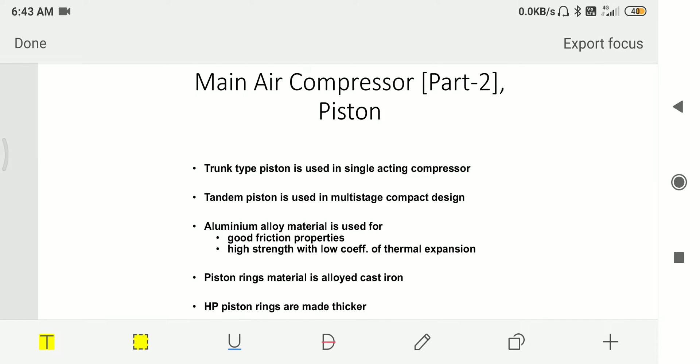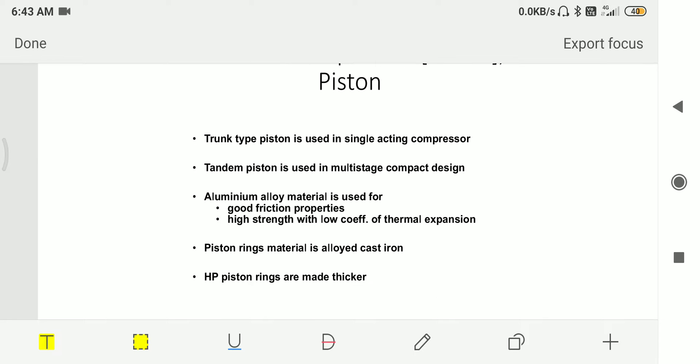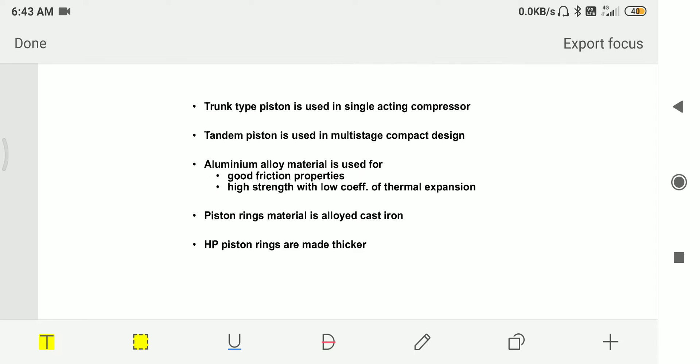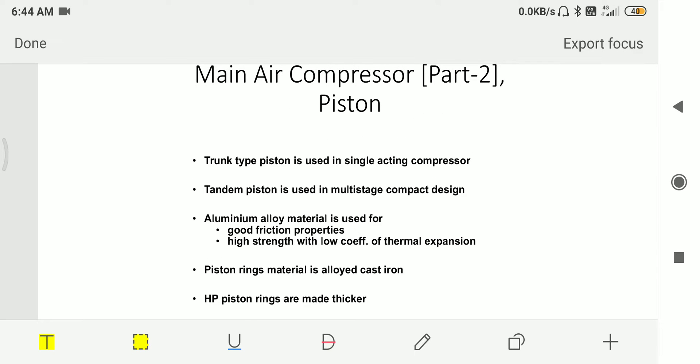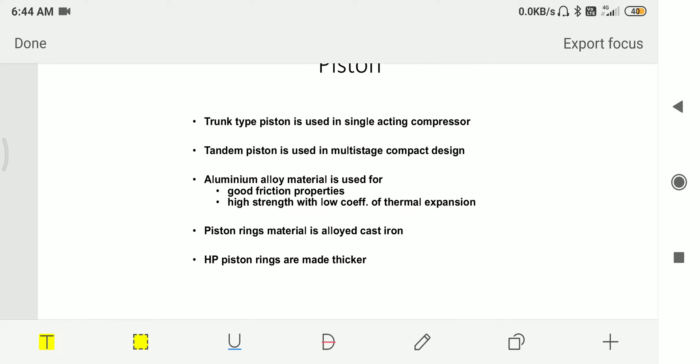Second component is piston. Trunk type piston is used for single acting compressors. Tandem piston is used in multi-stage compact design. The circuit diagram which we discussed before has tandem piston. They are mostly made up of aluminum alloy. They have good frictional properties, high strength with low coefficient of thermal expansion. Piston ring material is alloyed cast iron. High pressure piston rings are made thicker.